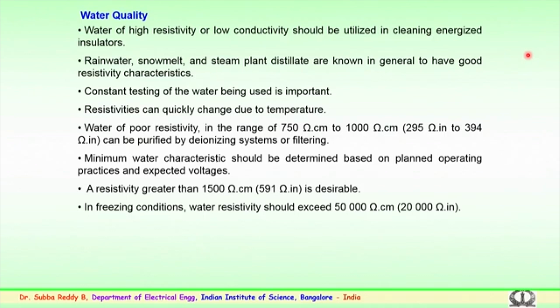The other is the water quality. Here again, the quality of water employed for cleaning the surface of insulators is important. Water of high resistivity or low conductivity is very important and should be utilized in cleaning energized or de-energized insulators. Rainwater, snow melt water, and steam plant water distillates are known in general to have good resistive characteristics. So, this type of water can be used for cleaning purposes.